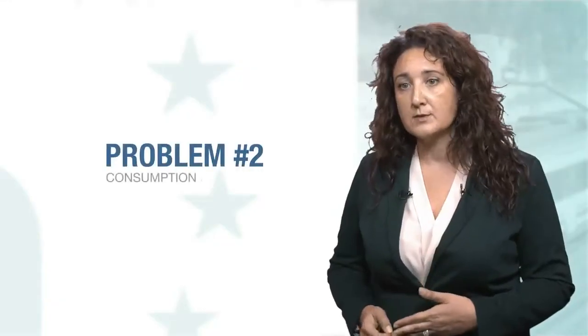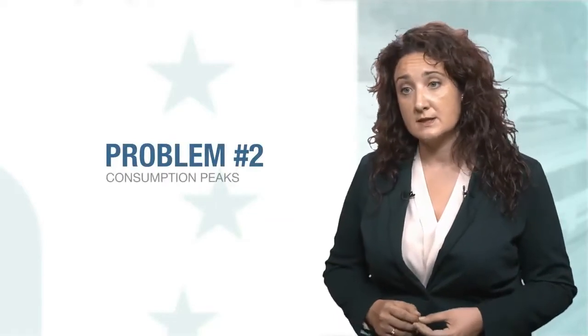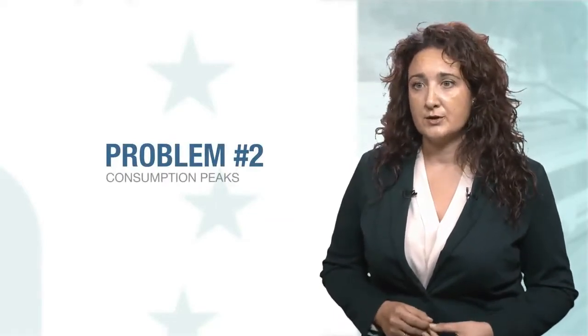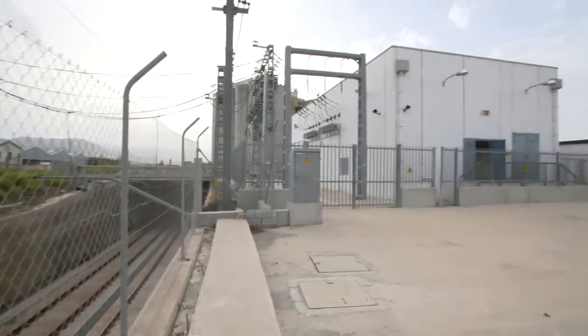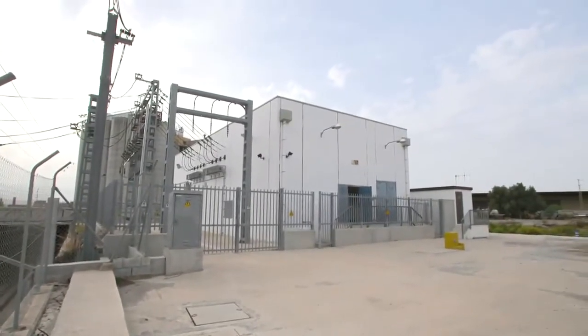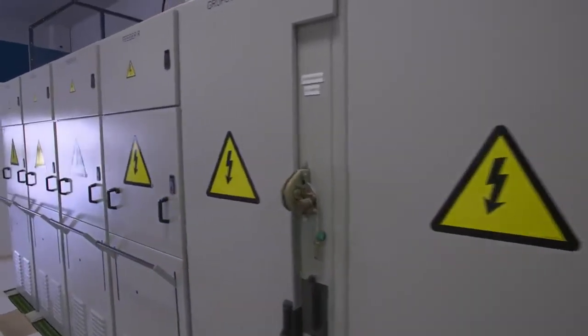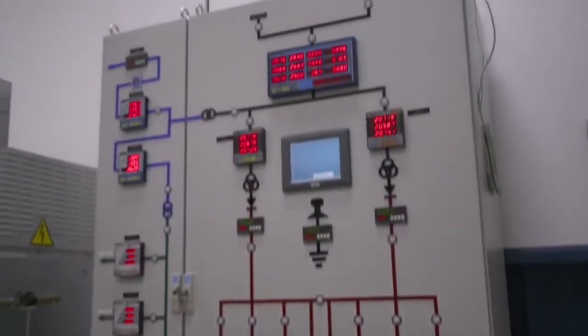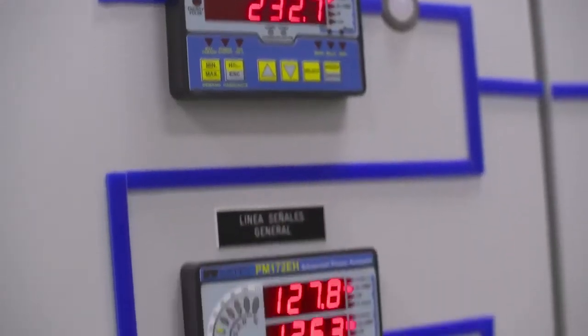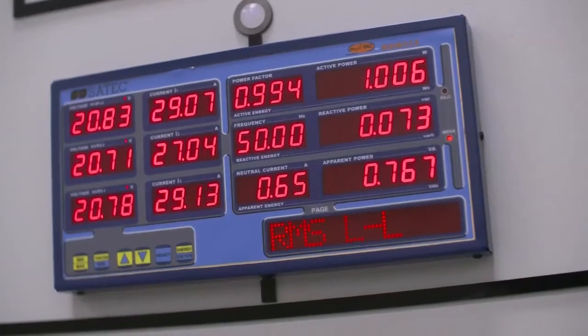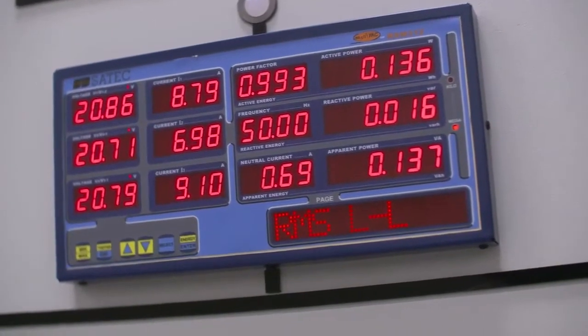Other common problems are the power peaks of consumption during the start of degraded operation, which force very high terms of contracted power, also at a high cost. Therefore, it is necessary to analyze the possibility of placing a storage system in order to reduce, even in degraded conditions, those peak loads, and also to determine the most efficient use of the recovered energy. Another important issue to analyze is the possibility of minimizing the terms of contracted power to reduce cost, which means a direct saving in the energy bill.